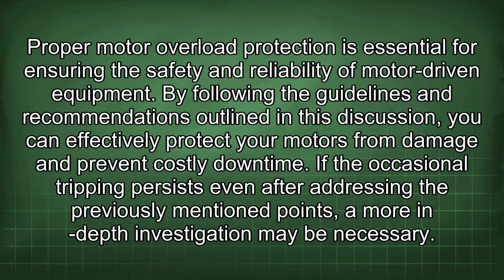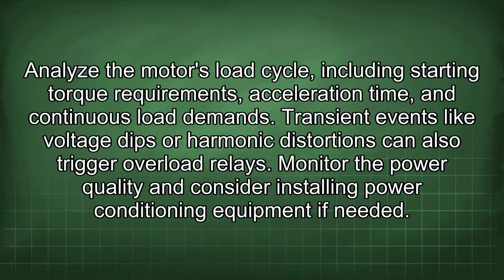If the occasional tripping persists even after addressing the previously mentioned points, a more in-depth investigation may be necessary. Analyze the motor's load cycle, including starting torque requirements, acceleration time, and continuous load demands. Transient events like voltage dips or harmonic distortions can also trigger overload relays. Monitor the power quality and consider installing power conditioning equipment if needed.